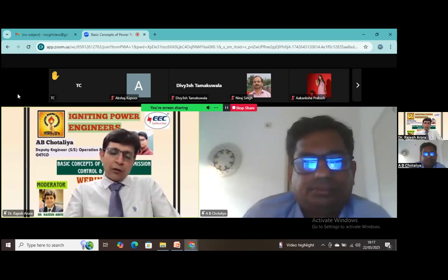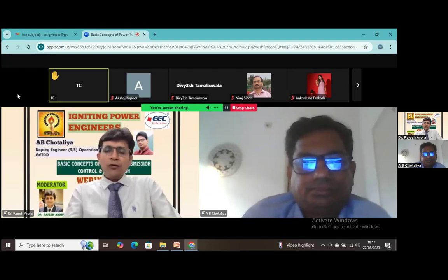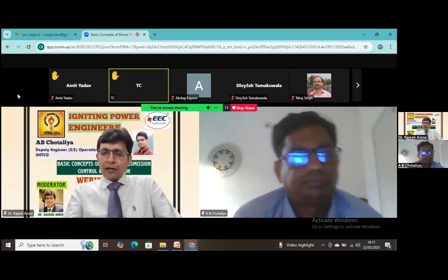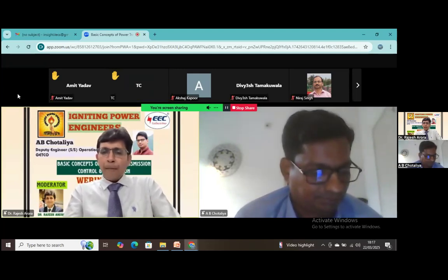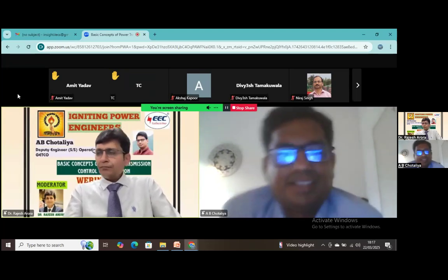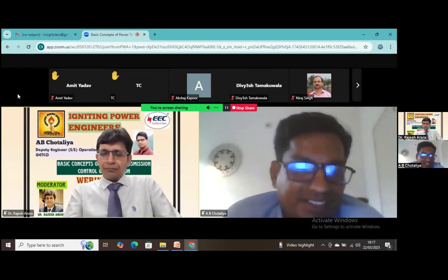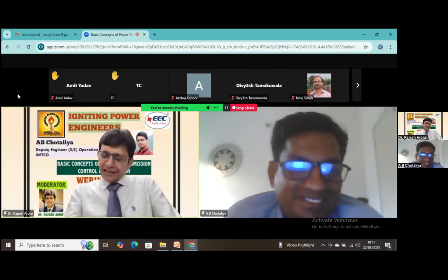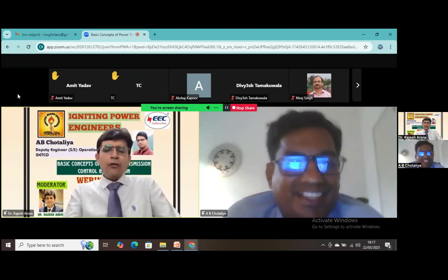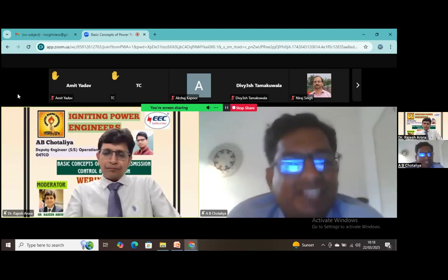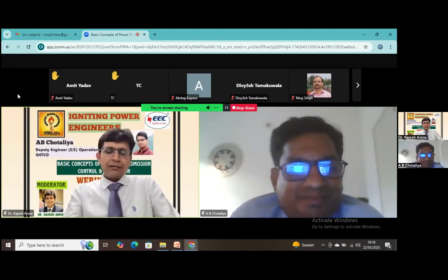We should isolate both. Abhishek ji, what do you have to say on that? What is your experience? Actually, whatever we require to isolate, that should be totally isolated. We should not take a chance at all. And a two pole MCB is required at that time. Agreed, sir.